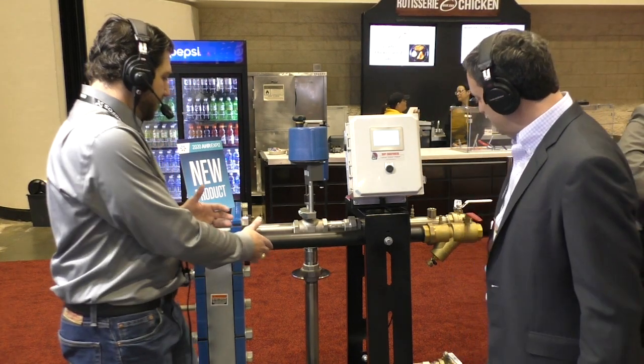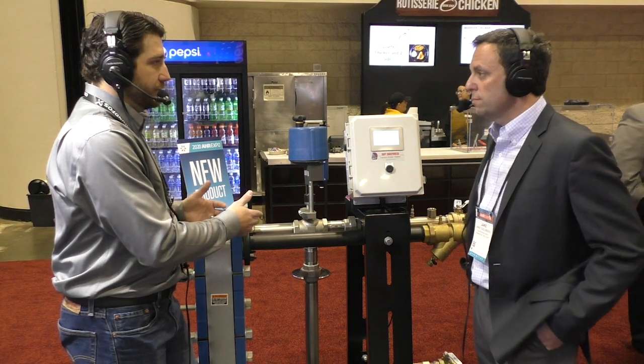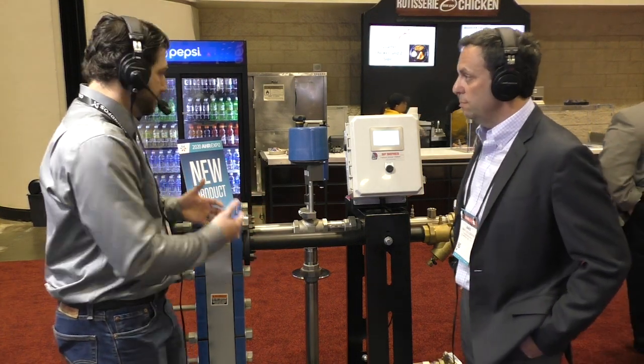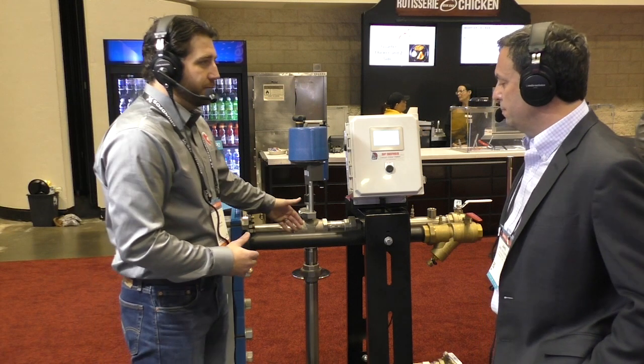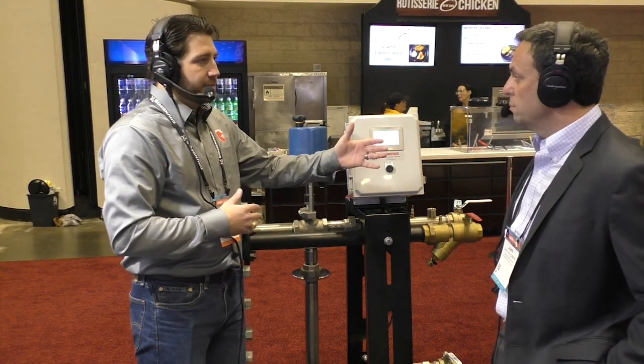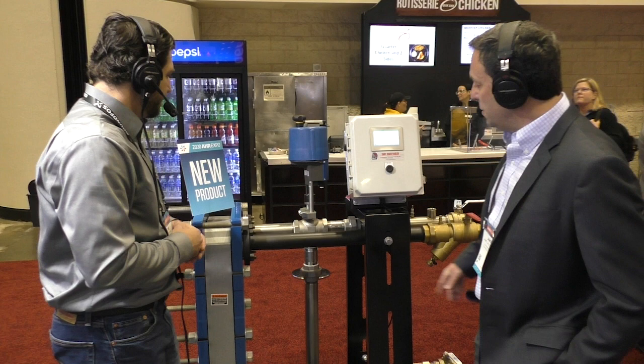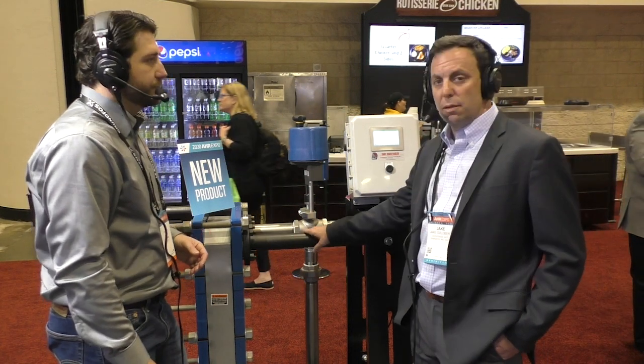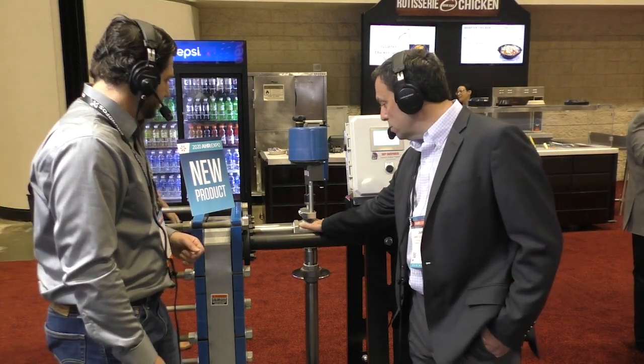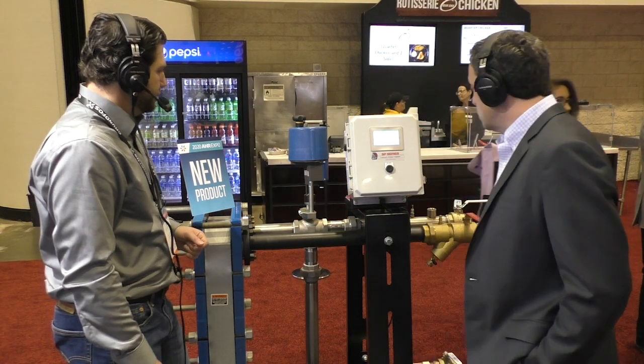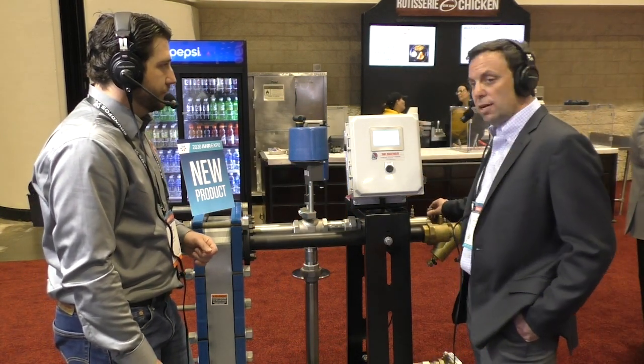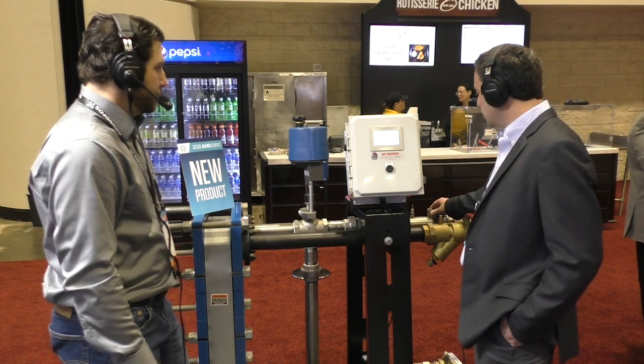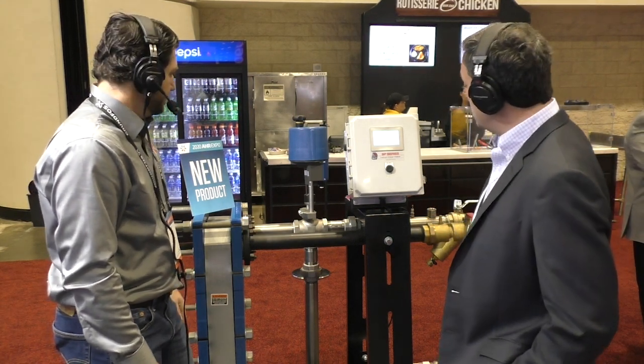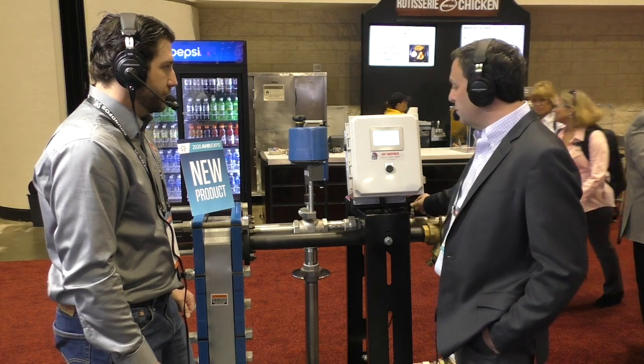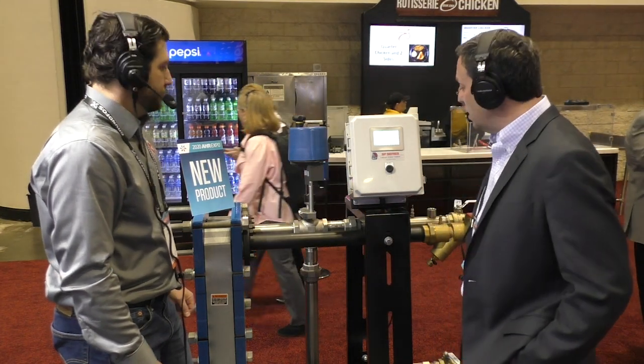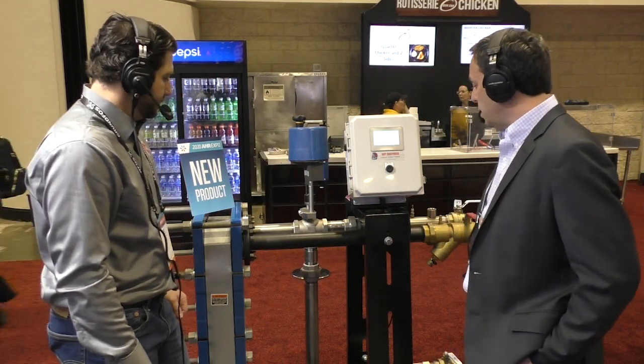So with this we're able to take the building heating hot water into the heat exchanger and use that heat with our mixing valve to provide constant domestic hot water, correct? Correct. We eliminate the two-way or three-way valve on the boiler side, and bring it on over to the domestic side. Getting this certified as an actual mixing station is our next step, which should happen in the next few months. Additionally, one of the exciting parts is it's a feed-forward feedback design - that's something new to our system as well.